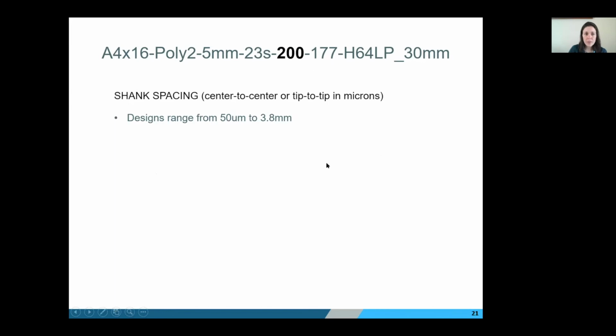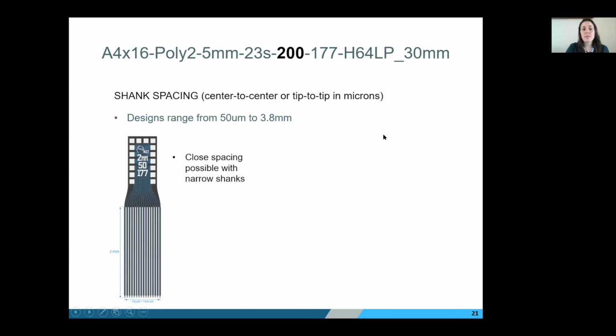The next part of the model number is the shank spacing now. So this is the center to center, or you could say tip to tip, spacing of the shanks. If the shanks are not the same length, it's hard to imagine the distance between their tips at the same depth. So you can think of it as center to center spacing. And for us, the design space ranges from 50 microns, which is quite small, to nearly 4 millimeters, which is quite large. So the 50 micron spacing is the Pareto probe that I had mentioned before, where each shank only has one channel. So keep in mind that the close spacing of shanks is possible when the shanks are very narrow. If the shanks get wider than 50 microns, then 50 micron spacing means you're inserting a solid block into the tissue, which is not ideal.